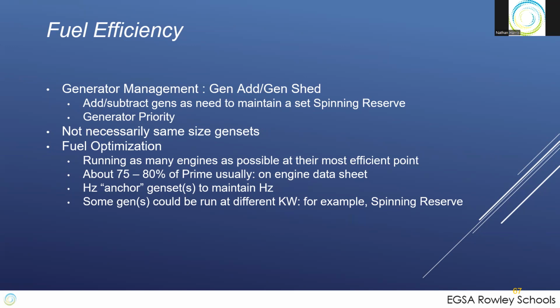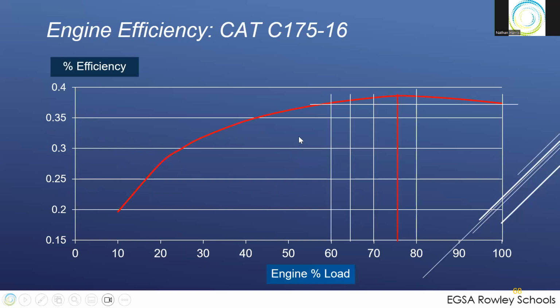So you have certain anchor gens that hold it. Let me talk a little bit more about this. Let's take a look at some numbers real quick first. Here's an actual curve. I got this from a Cat C175-16 because it's available online. I'm not picking on Caterpillar; I just happened to find it online, so I used it. This is the efficiency data for this machine. It's showing somewhere just shy of 40% efficiency, maybe 37, 38% efficiency at 75% of the engine nameplate. You see it actually decreases to lower efficiency at 100%, and lower efficiency on this side. So you want to optimize that and run at this point.